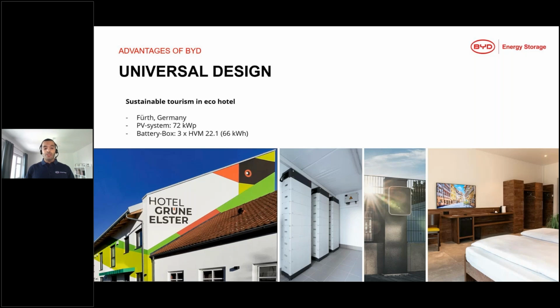Because a hotel generally needs more energy, with more rooms, it also needs a bigger battery. In this case it's still the same battery type, the HVM, but instead of 16.6 kilowatt hours, that HVM system has 66 kilowatt hours. This is achieved by extending with additional modules in a tower, but also by connecting multiple towers in parallel - up to 3 towers, giving a practical capacity of 66 kilowatt hours in this case. So this example proves that the same battery used for residential applications can also be used for small commercial applications, because it's very flexible.